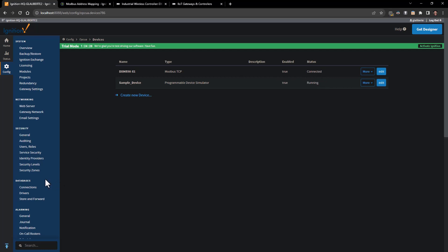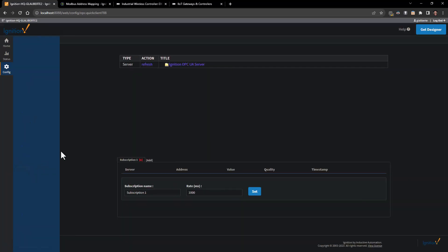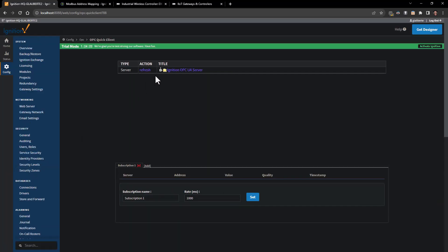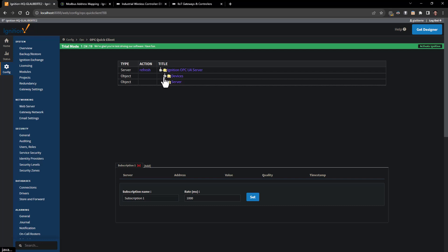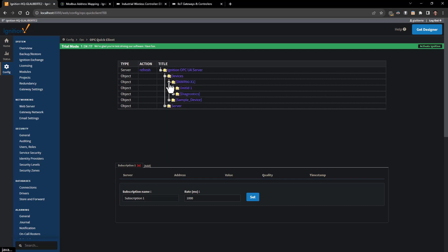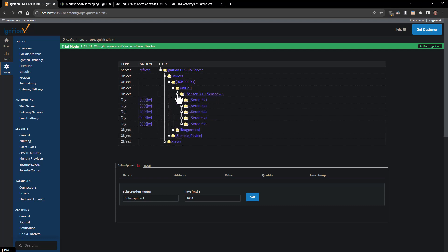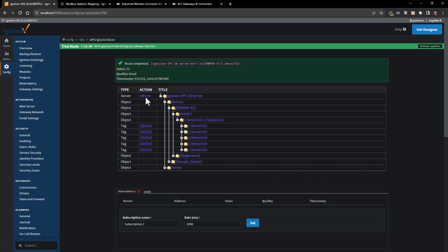Then all we need to do is come down and we can go to the OPC client, click on the quick client. We can see that if we expand this out and go under devices, there's our device name. We also have our unit ID 1. You can see our tags that were created inside of here, and these are the five registers that are being pulled.